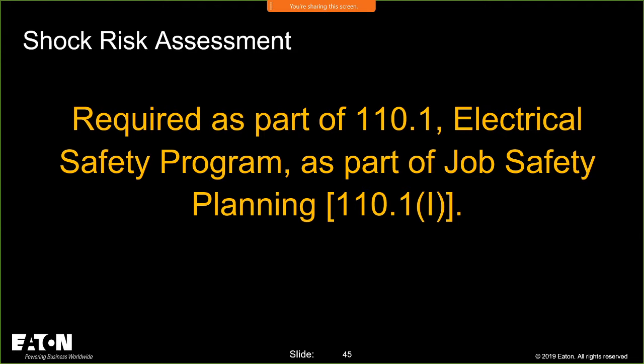It's required as part of 110.1. So if I look at 110.1 in 70E, remember, 70E is laid out very similar to the National Electrical Code. 110 are your general requirements for electrical safety related work practices. So 110 applies generally to all areas. And so this is where you're going to find your electrical safety program.